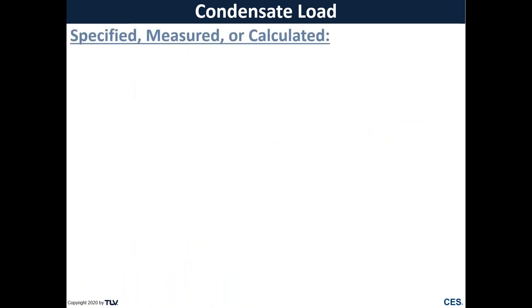So if we look at condensate load, condensate loads are usually either specified on a data sheet, or we can measure or calculate these loads. There's actually three different condensate loads that we need to take into consideration. The first being our startup load, which is typically the maximum load that we're going to see on an application.